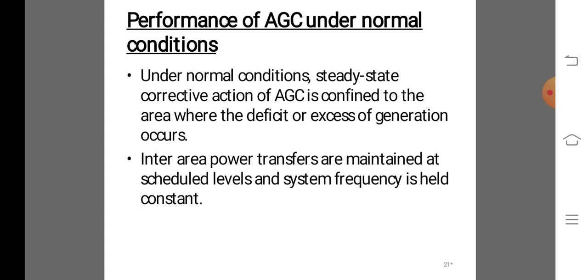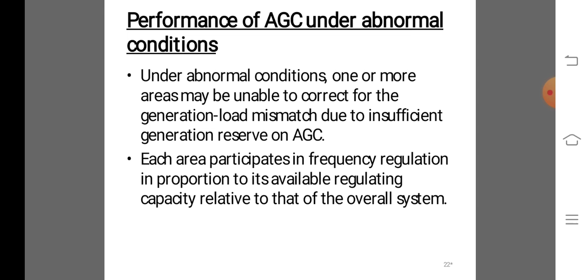Next, performance of AGC under abnormal condition. In the governor system, both the areas start acting simultaneously to change generation in their respective areas under abnormal condition. One or more areas may be unable to correct for the generation load mismatch due to insufficient generation reserve. In AGC, each area participates in frequency regulation in proportion to its available regulating capacity relative to that of the overall system.